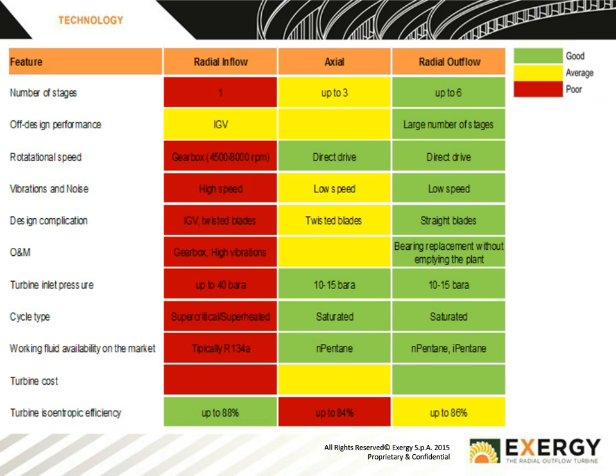The first thing is number of stages. A radial inflow turbine, for your information, is a single stage, high-speed turbine where the fluid moves from the outside to the inside. This basically looks a little bit like a turbocharger running in reverse, to give you an example. So it is a single stage, and it relies on its high speed to give you a good efficiency. And it does have a higher efficiency, but it tends to have a higher efficiency at very discrete conditions. So it works at a very set condition at a high efficiency. An axial turbine is the one we've already described. That can have up to 3 stages, and the radial outflow turbine can have up to 6 stages. So that higher number of stages tends to give us a higher efficiency and a variety of operating conditions.